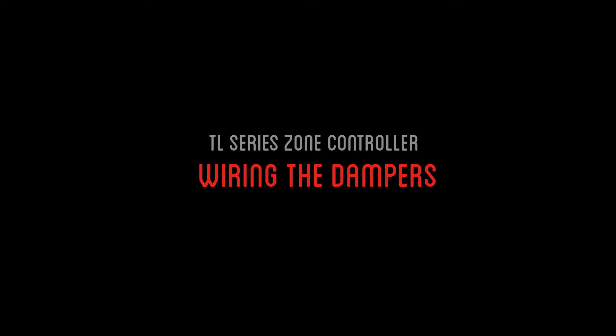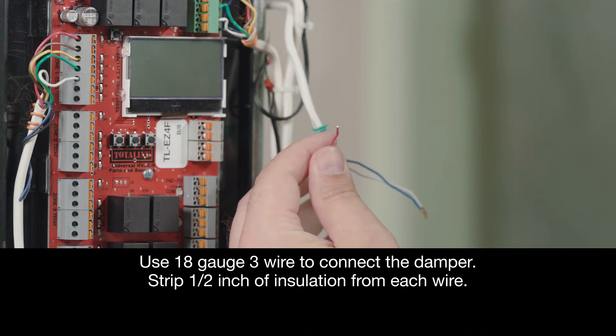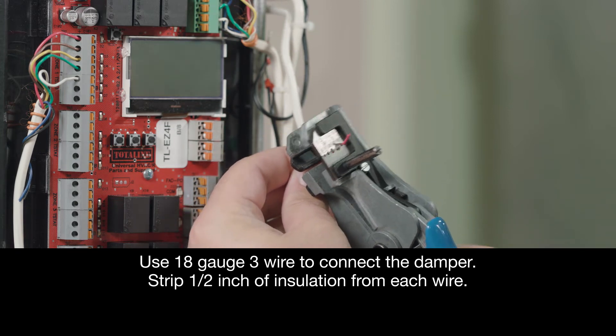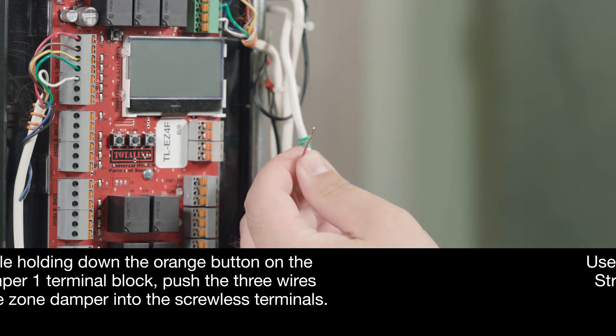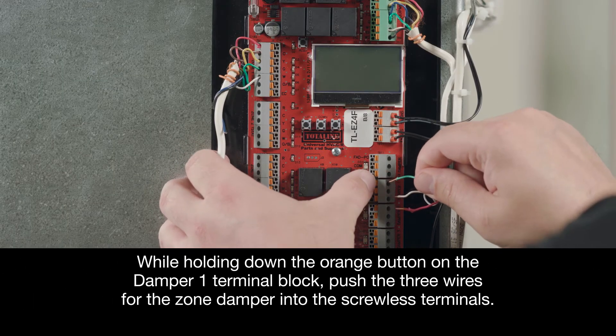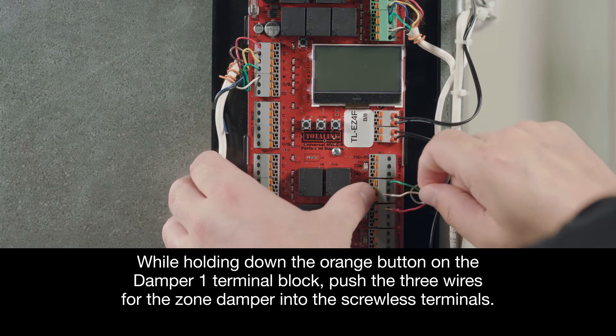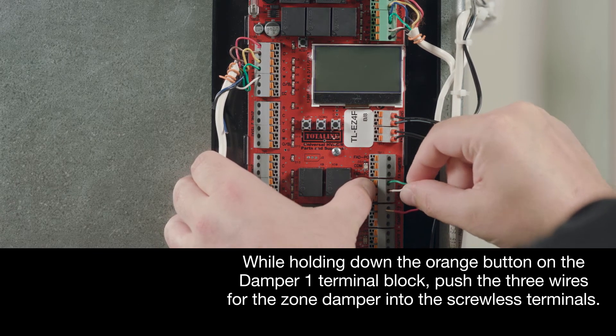Now, let's move on to wiring the power open, power close three-wire dampers. We'll use 18-gauge 3-wire to connect the damper. First, we'll strip a half an inch of insulation from each wire. Then, while holding down the orange button on the Damper 1 terminal block, push the three wires for the zone damper into the screwless terminals.